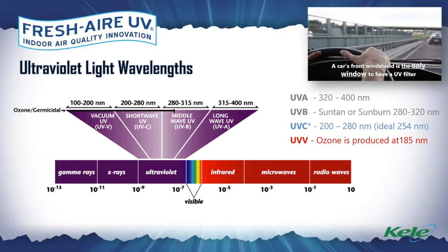So the technology and the process of UV disinfection is always based on the accumulation of a dosage. In this case, one sunburn is not an issue, but multiple sunburns with that accumulation does pose the issue. Now, Fresh-Aire UV systems produce UVC light at the 254 nanometer wavelength. Now, we're never, as a planet, in contact with UVC light.